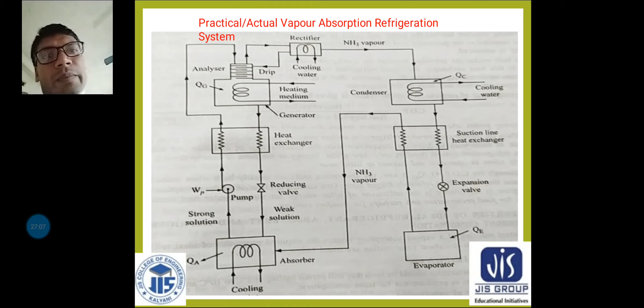So the following points about the vapour absorption are very important, and how it is operated. Here basically we have used two heat exchangers, one analyzer, one rectifier. In the rectifier the water is separated and sent back to the generator again by the help of a drip pipe return. Okay, and in the heat exchanger, the function of the heat exchanger you have seen, the function of the analyzer you have seen, and this is how you can improve the efficiency of the VARS, vapor absorption refrigeration system. Okay, so this is all about the practical vapor absorption refrigeration system.